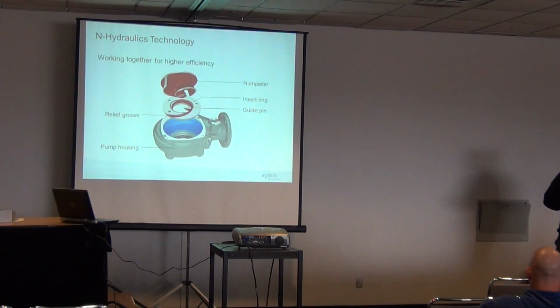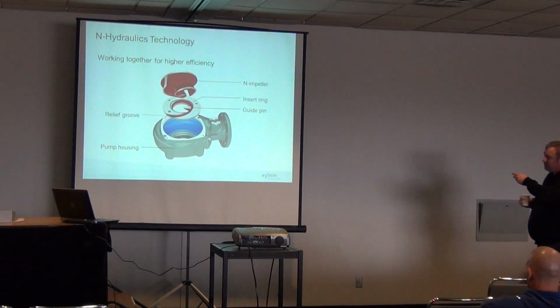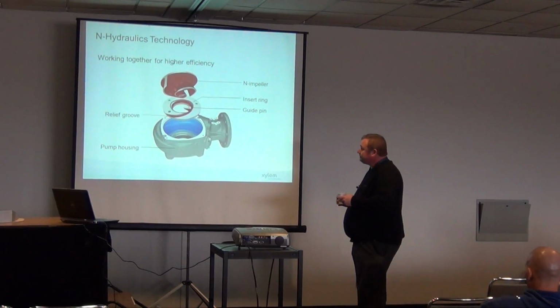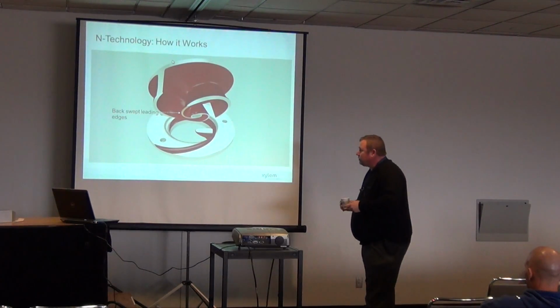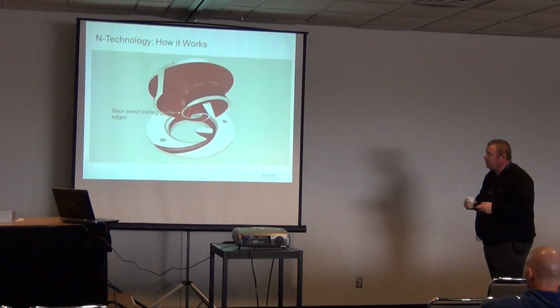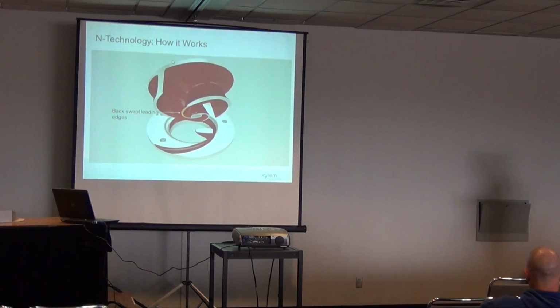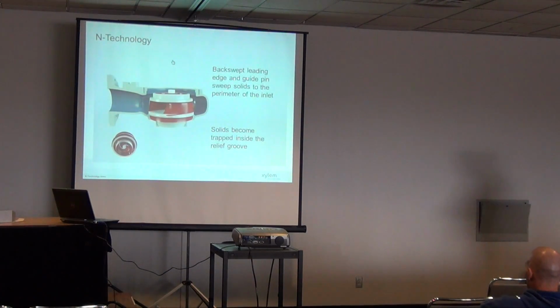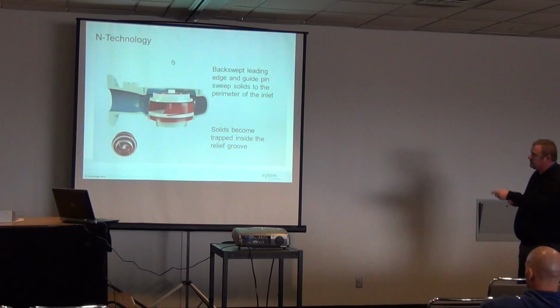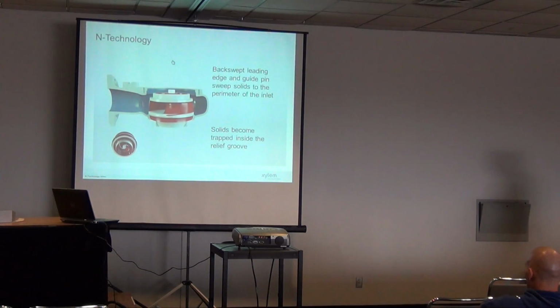Now, as an operator, if you don't have some sort of system or flow meter on your station, you're not necessarily going to know that. So sustaining efficiency with this wet end is a big part of the savings that you can have. So what does it mean? We've got a back swept leading edge on that impeller. It's open, it's not double shrouded or closed like you see with a channel impeller. In this area here we have a relief groove and this guide pin that you saw in the video that actually guides the material into the pump and passes it through. The solids get trapped inside that relief groove and pass through the wet end of the pump, sustaining that efficiency, not allowing any soft clogging.